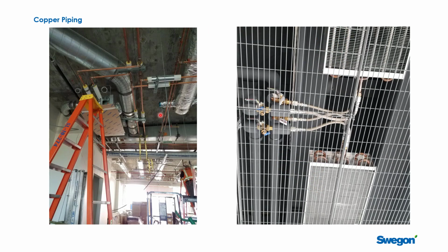And we talk a little bit about what kind of piping systems do you see, what material is used. Copper would certainly be the most common. You can see that in this project in here, where they're starting to rough in the piping over close to the chill beams here, and the ductwork starting to come in. Connections are on. Normal to see chill beams supplied with protection during assembly to protect the finished surfaces, and having little plastic bags over the air inlets so we don't fill them up with construction dust.